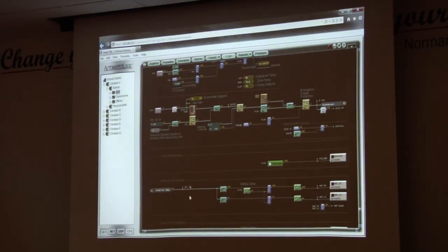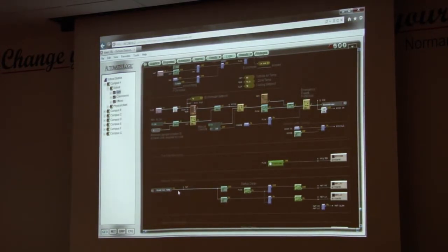So when I do this and I come down here, it says, well, here, my mixed air temp is 25. Well, right off the bat, I could tell you if my mixed air temperature is 25 degrees, I do want the outside air closed because something's wrong. I'm telling you, if my economizer says 0 on the outside air, right, 100% return, and I have a 25-degree mixed, I don't care what's happening, I'm telling you, those dampers are slipping. Something's open. My screen may say 0, but somewhere that actuator's lost grip of that rod, or the rod's broken, and that outside air damper's wide open, all right?